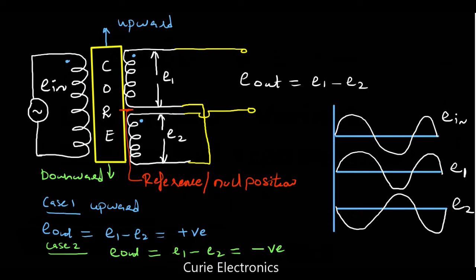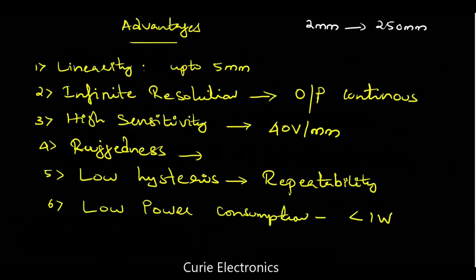Let's see quickly the advantages and disadvantages of this LVDT. I forgot to mention, LVDT is used to measure distance, from 2 mm to 250 mm. Advantages: linearity - up to 5 mm it is highly linear. What about resolution? Infinite resolution, because it is an analog sensor giving continuous output. So it is known as infinite resolution, and it has high sensitivity. High sensitivity means it gives more voltage for a very small displacement, that is, 40 volts for 1 mm displacement.